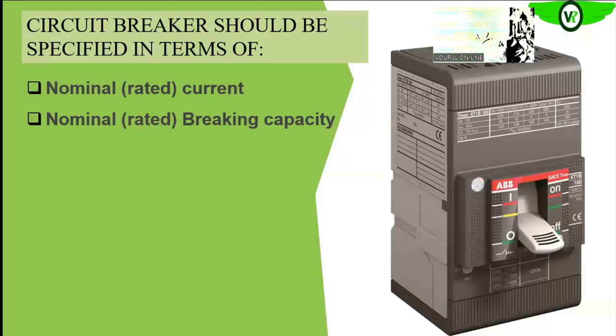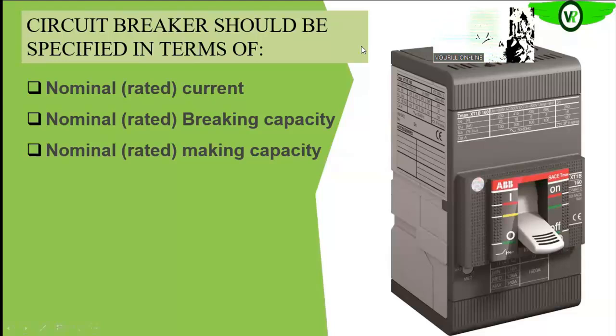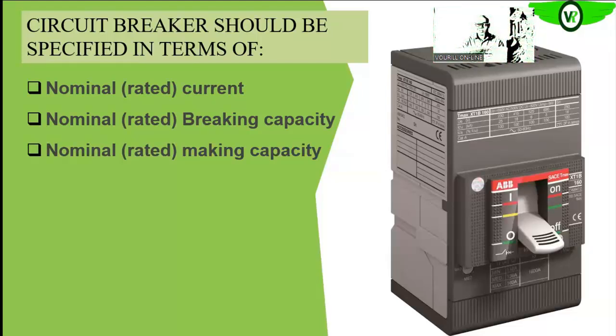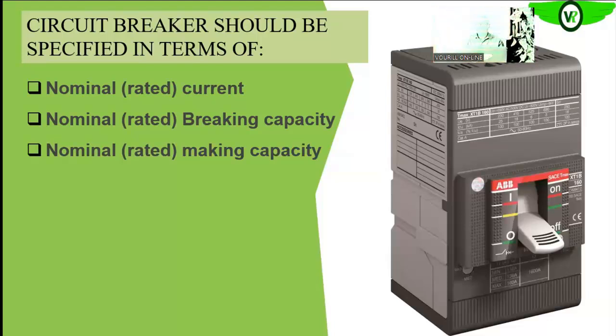The other term to understand is the nominal rated making capacity of the circuit breaker. Remember that the circuit breaker can close when the fault current is still in the circuit — it can close on the fault. If that happens, the circuit breaker should not be damaged; it should be able to withstand that fault current while making or closing the circuit breaker without causing any damage. The maximum rated making capacity is always stated in kilo amps.